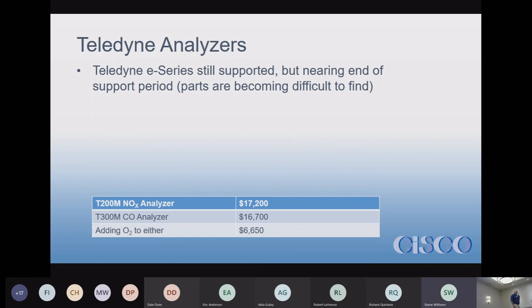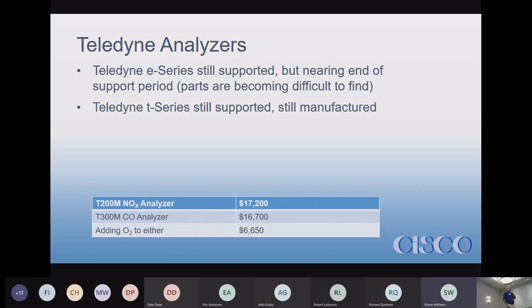I talked to Teledyne yesterday to verify information on the T-Series. They said, please — if you have an E-Series analyzer, they technically still support it, but they're having trouble finding parts for them. They ask you to get rid of the E-Series and move on. The T-Series analyzers are the T-200s, T-300s, and T-100s depending on where you are and what kind of analyzer you have — those are the most common ones, covering NOx and CO.